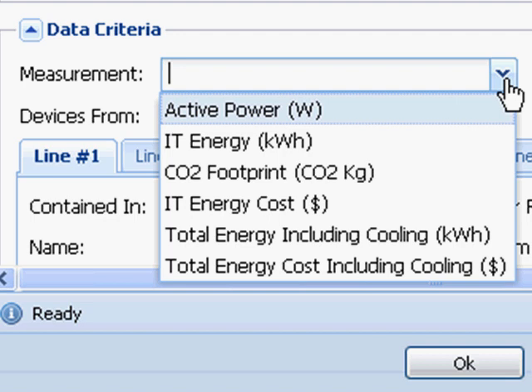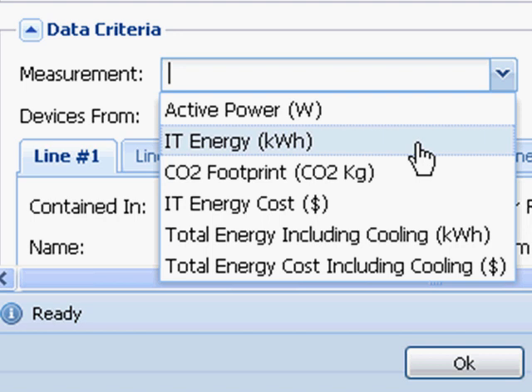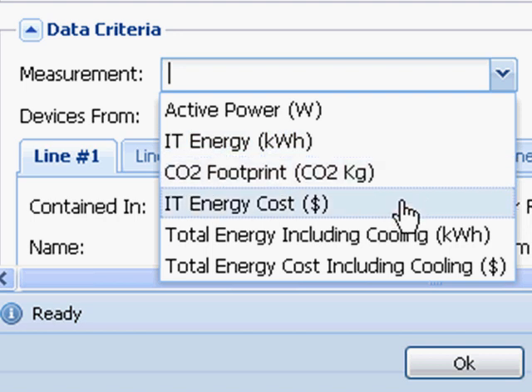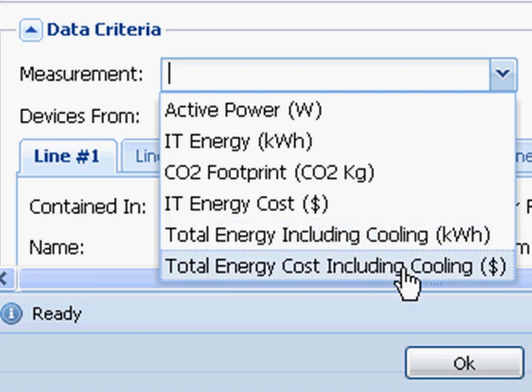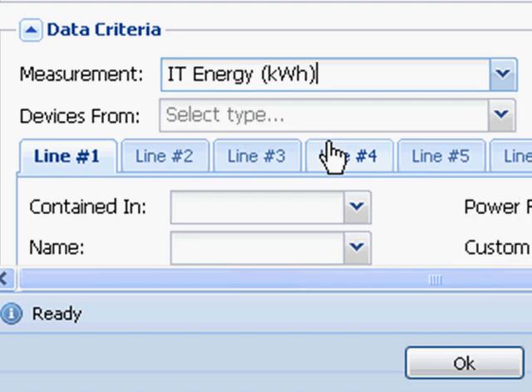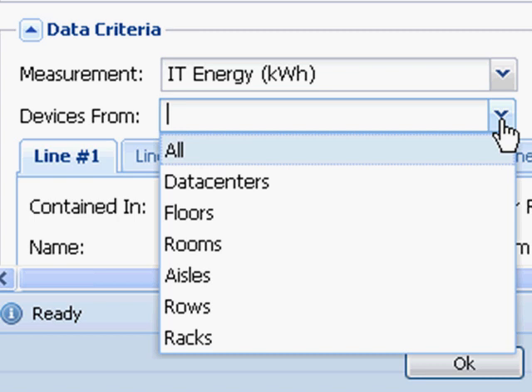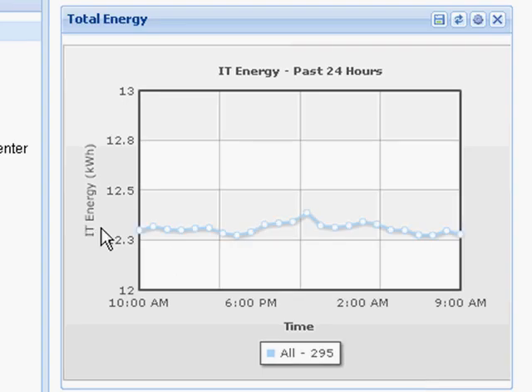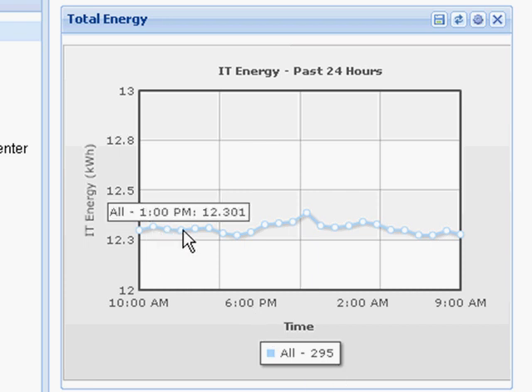This is where I select my measurements. I can select active power in watts, IT energy in kilowatt hour, carbon footprint in kilograms, IT energy cost in my local currency, total energy including cooling in kilowatt hour, or total energy including cooling in my local currency. Since this is an energy report, I'll select kilowatt hour. Now I select my containment of devices — I'm going to select all, and I can simply create a chart that graphs my total energy in kilowatt hours for all IT devices in my data center.